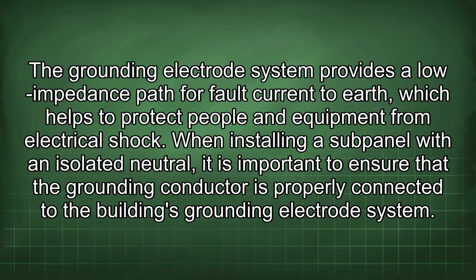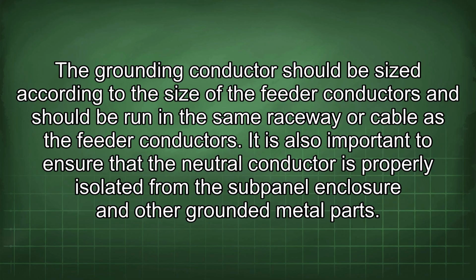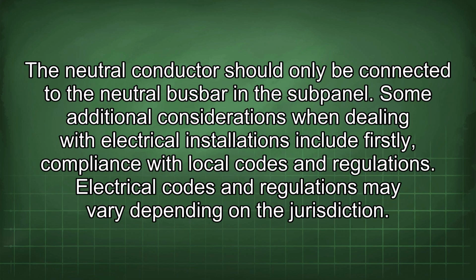When installing a subpanel with an isolated neutral, it is important to ensure that the grounding conductor is properly connected to the building's grounding electrode system. The grounding conductor should be sized according to the size of the feeder conductors and should be run in the same raceway or cable as the feeder conductors. It is also important to ensure that the neutral conductor is properly isolated from the subpanel enclosure and other grounded metal parts. The neutral conductor should only be connected to the neutral busbar in the subpanel.